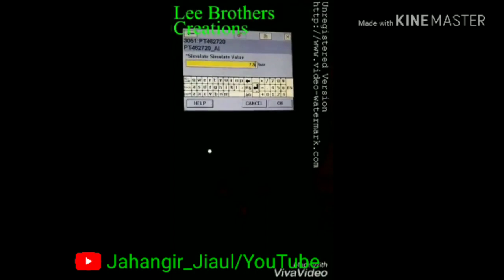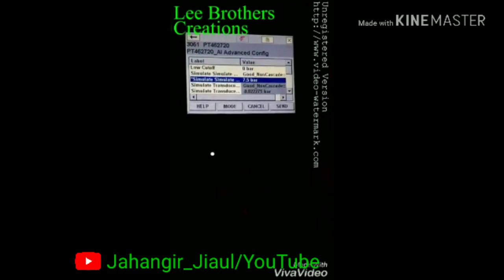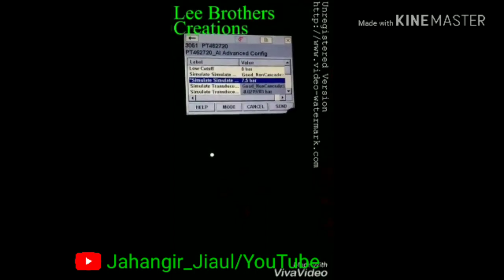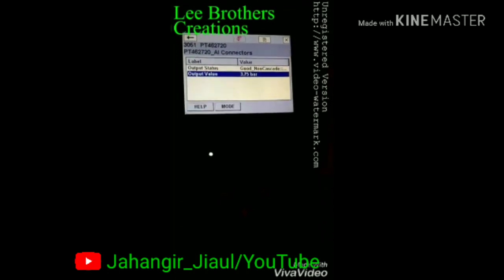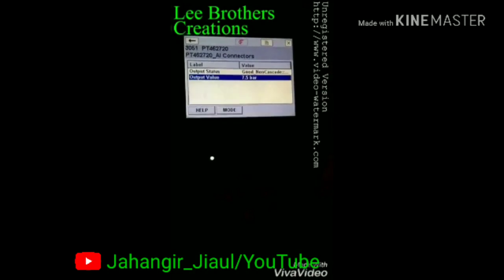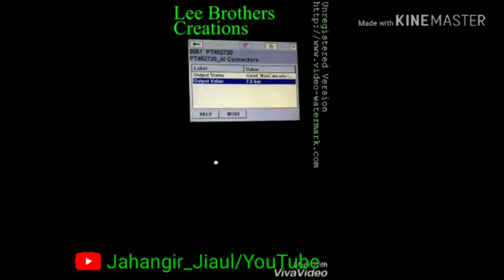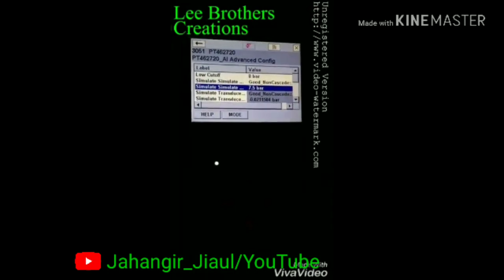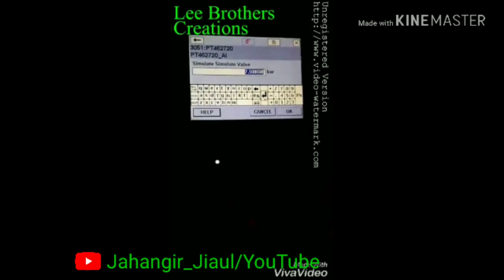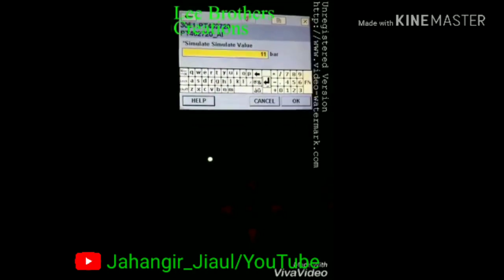Now I want to set the value for 50%, which means 7.5. Enter the value for 50%, click OK and click send. Now you can see the display side is showing the value as 7.5 for 50%. For 75%, I enter that value in the advanced config and select the simulation value: 11.25, which corresponds to 75%.